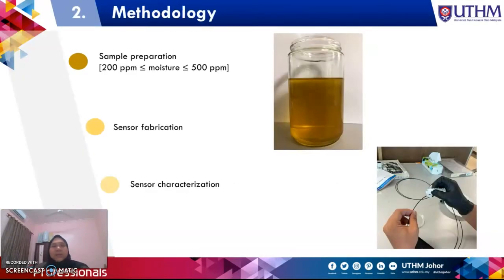In the methodology, we have three major steps. The first is sample preparation, where we prepare four different moisture contents in the transformer oil: 200 ppm, 300 ppm, 400 ppm, and 500 ppm. The second step is sensor fabrication, where we fabricate our POF cable to act as a moisture sensor. The last one is sensor characterization, where we test our fabricated sensor in the samples that we prepared in the first step.